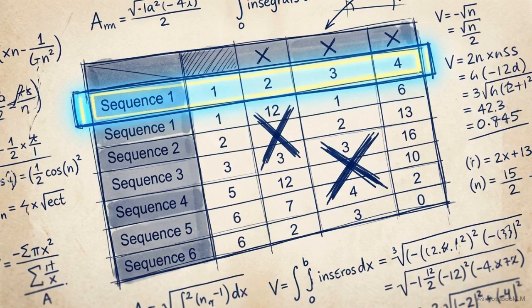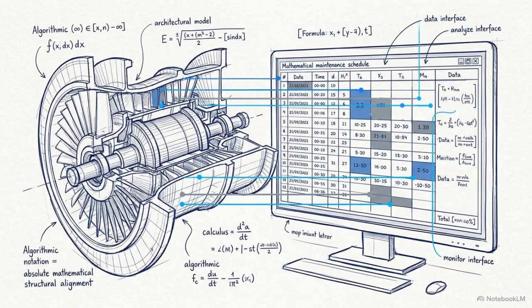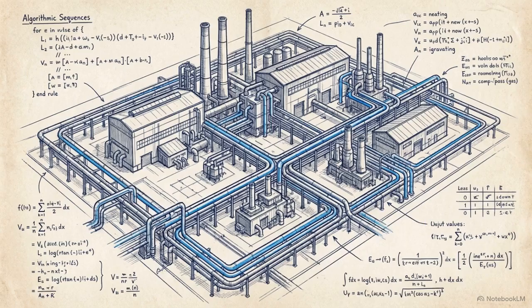On work order 13, the cycle resets. 13 fails to divide evenly by 12 or 3. The algorithm falls back to sequence 1, and the basic check is issued. The divisor algorithm gives planners the ability to stack infinite, highly complex maintenance cycles onto a single asset with absolute mathematical certainty. Individual asset algorithms handle the micro-level logic, but macro-level physical plant architecture requires grouping work across multiple machines simultaneously.